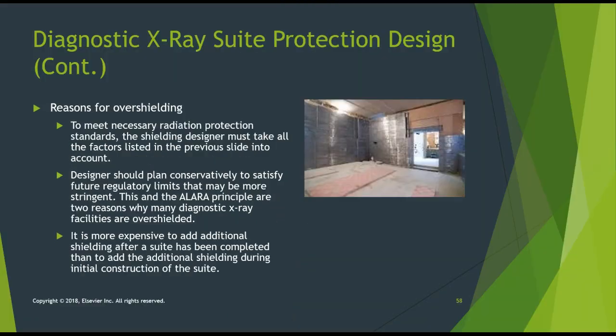Okay, as a result of all of these guidelines and recommendations, when you build an X-ray suite, you always err on the side of caution, so you over-shield a room based on what you think the room is going to be utilized for, who's going to be on the other side of the wall, if it's a control area on the other side of the wall, or if it's general public. So all of these things go into consideration, and it is much more affordable to put the lead lining inside these walls under construction than it is to add shielding later. So they over-shield when they construct these suites.